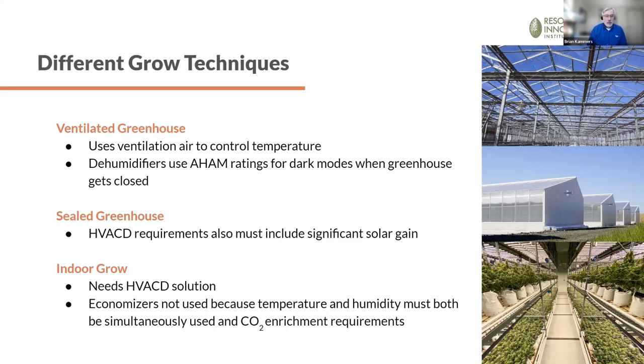When we talk about these different growing techniques, we're really tied to systems of growth where utility companies get involved, so we're not talking about outdoor grow here. We're talking about ventilated greenhouses, which historically just use outdoor air to control the temperature in the space. At nighttime, when humidity would build up, they'd use a dehumidifier, typically a portable one, rated using the Association of Household Appliance Manufacturers rating, which is 80-degree temperature and 60% relative humidity. As temperature and humidity go down, these refrigeration or dehumidification systems have less and less capacity for removing moisture.